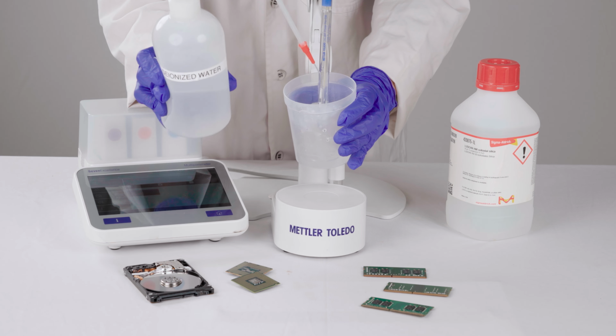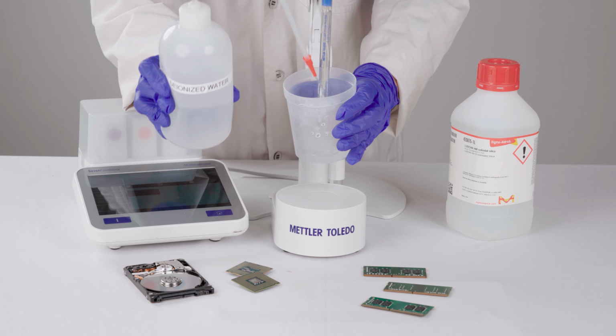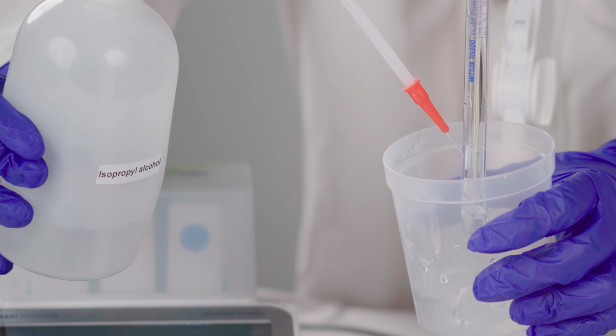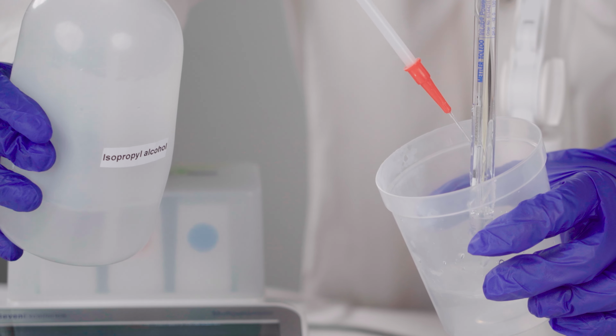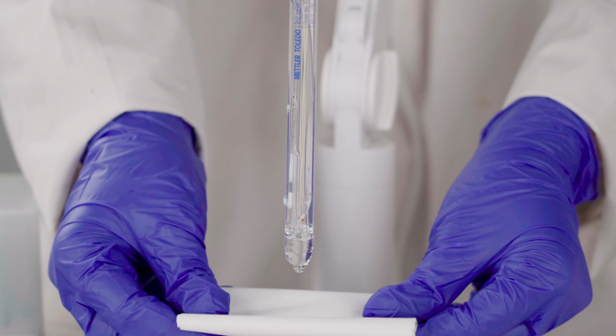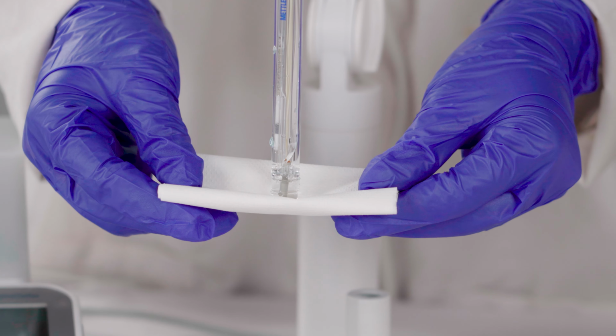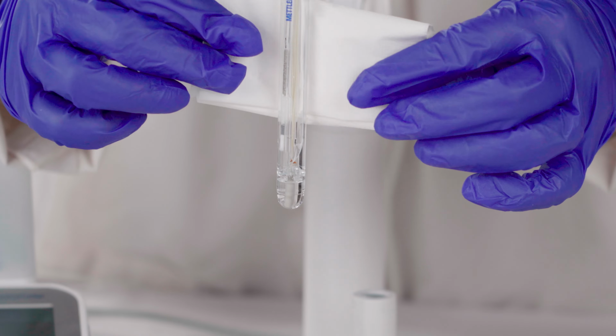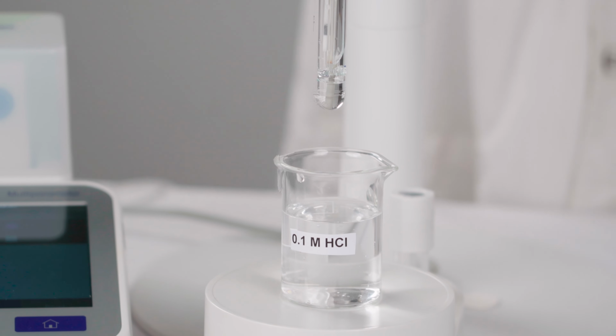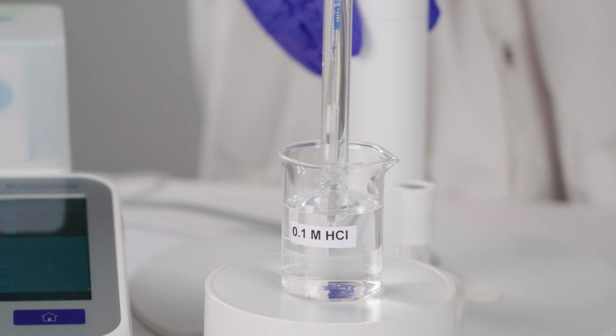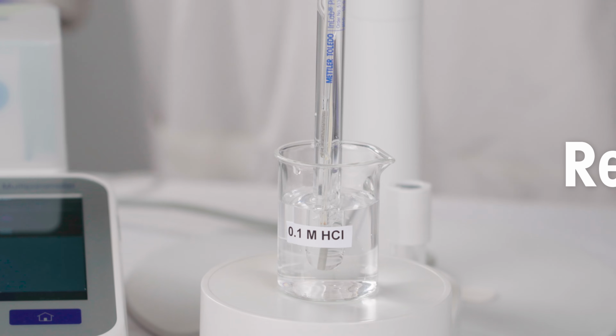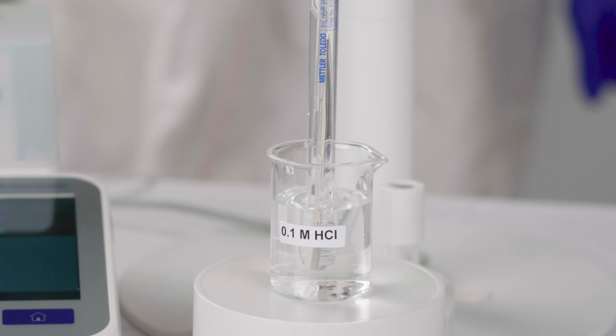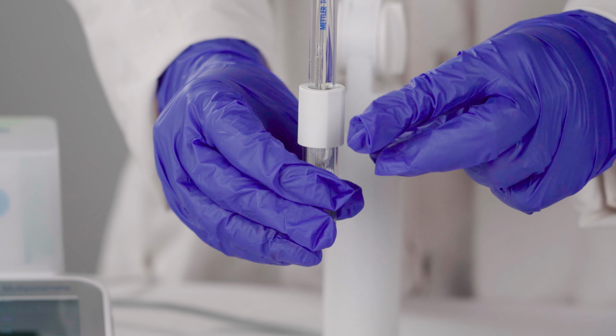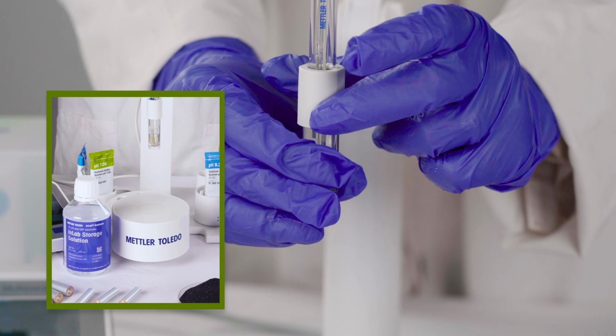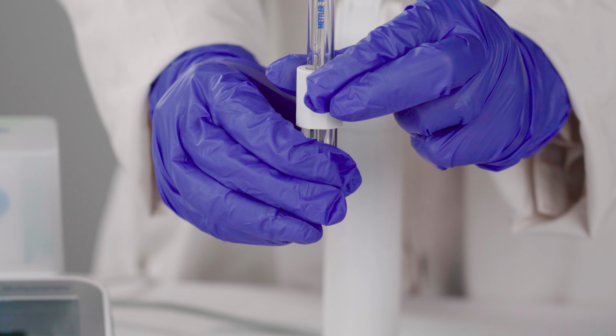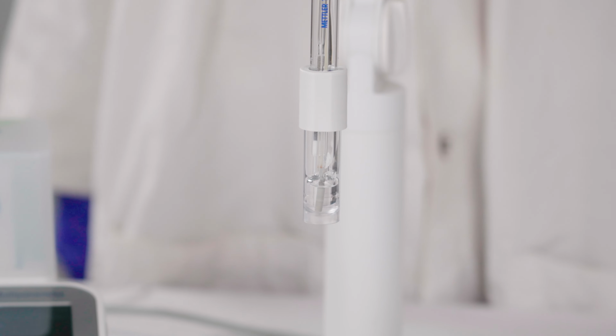After each measurement, don't forget to clean your sensor using deionized water. And for a deeper clean, isopropyl alcohol or ethanol can do the trick. But remember, don't rub the delicate surface of the sensor, treat it with care, and gently blot it dry with tissue paper. To keep your sensor performing at its best, periodic reconditioning in 0.1 molar HCl solution and recalibration is a must. And when it's time to store your sensor, the wetting cap filled with InLab storage solution is your best friend. Don't even think about storing your sensor in distilled water or letting it go dry.